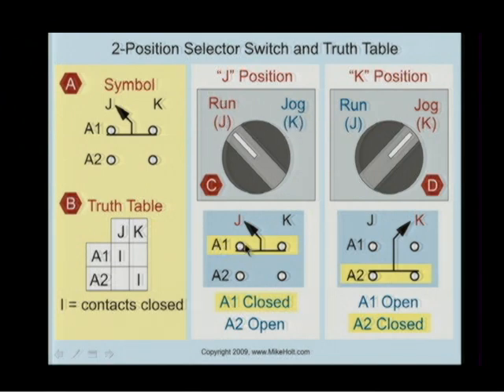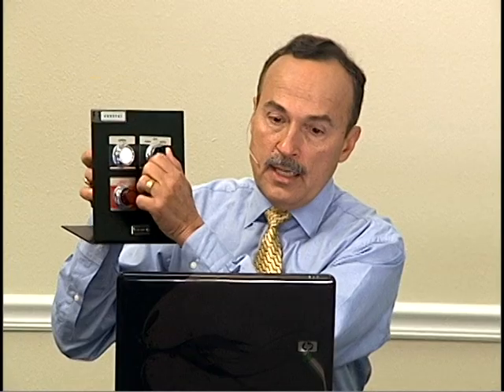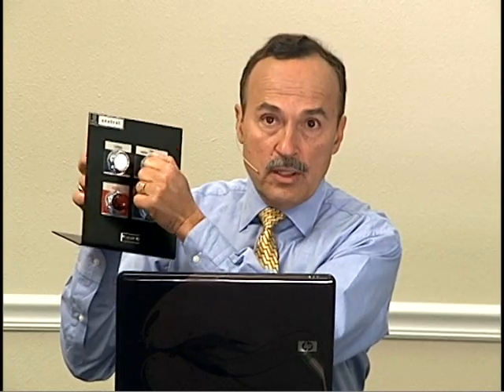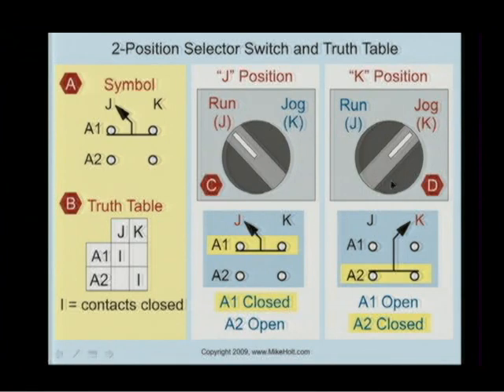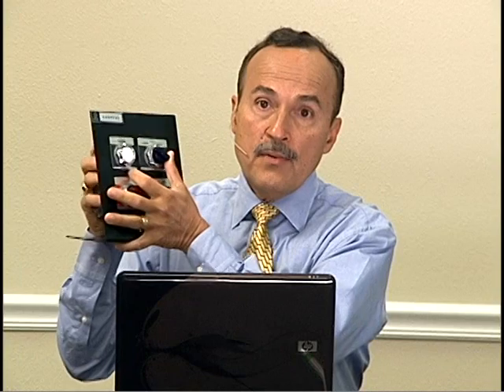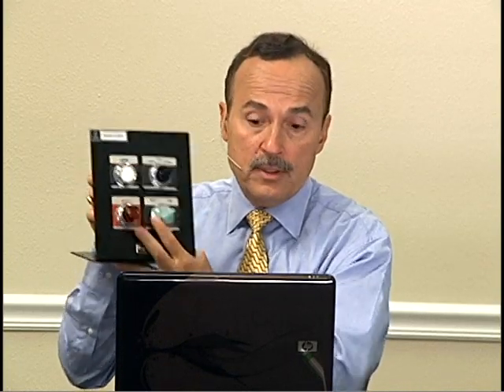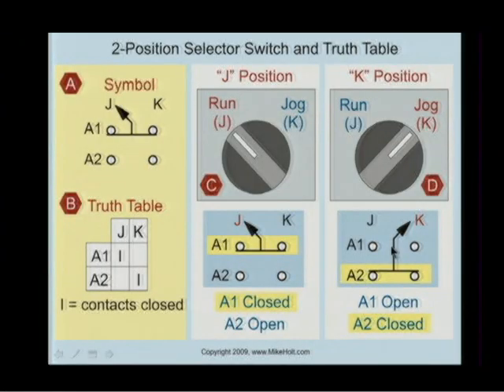The A1 contacts in the J position are closed. If you go into the K position, you turn the selector switch to the other side, right here. So let's say that was in the J position, I turned it to the left. That's going to give me a set of conditions. In the J position, A1 contacts are closed, A2 contacts are open. Then if I take the same exact switch and go in the other direction, that's going to put us in the K position. That means that A1 contacts now will be open and the A2 contacts will be closed.